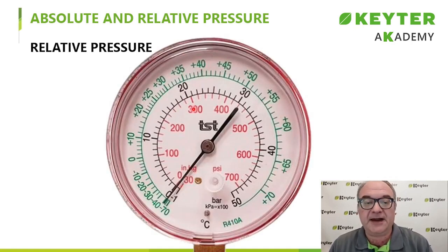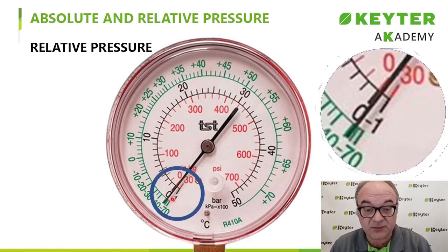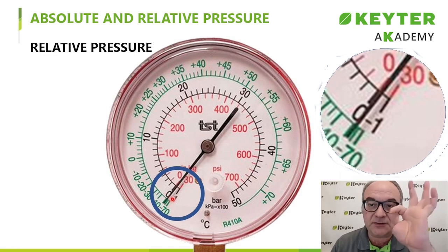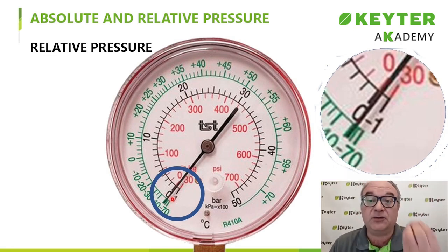That's why on the dial of pressure gauges, we have this little dot where we meet a pressure of 0 bars and a pressure of -1. Well, in this case, the pressure gauge measures gauge pressures. So 0 would actually be 1 bar absolute inside the tank, and -1 would be equivalent to 0 absolute bars inside the tank. That's why when we evacuate a machine, we don't stay at 0, but we go down to -1, which is actually when we have 0 bars inside the tank or inside the pipe, in this case.